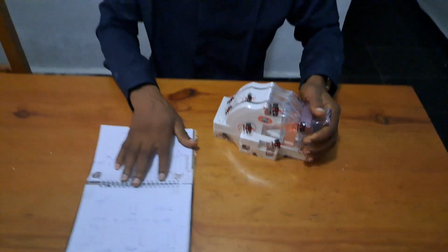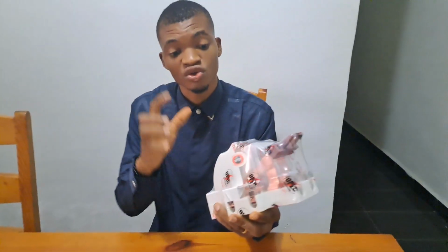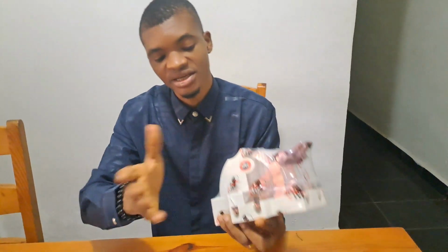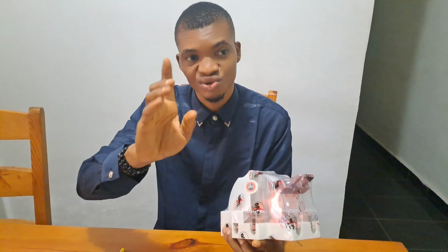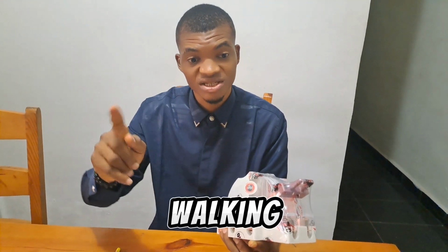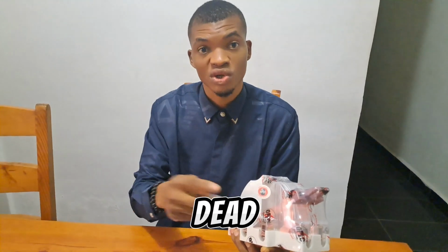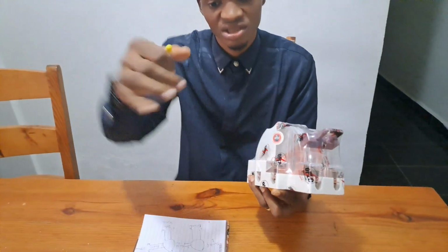So bring up the camera, let me demonstrate it to them. Like what I said, you have three supplies that you want to supply to the house, and I use here as my NEPA, I use this place as my generator. So what it means is that whichever one I want to go to the house, I will first select it here. From here I will feed it to another changeover switch. From the changeover switch, if I want it to remain on NEPA or gen, I push it there. If I want it to be on solar, I will bring it down to solar. So what it means is that my input to the solar, which is for charging, should come here. Either I pick it from here or I pick it in the next changeover.